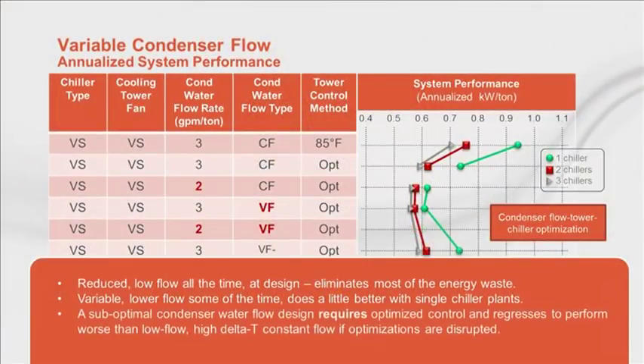There is one final caveat. A suboptimal condenser water flow design requires optimized control to achieve best efficiency levels. If the control were removed at some point, for some reason, the efficiency of a variable flow condenser system regresses to become worse than low flow, high DeltaT constant flow.